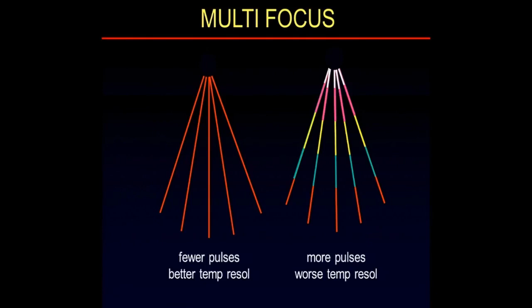Single focus looks like that. Multifocus looks like this. If I have five focal points, I need five pulses. So which one makes a quicker frame? Single focus. Which one makes a better image? Multifocus. So you're not going to have a question that says, does single focus improve resolution? Because the answer is yes and no. It gives you a higher frame rate, but the image isn't as good. We control this.